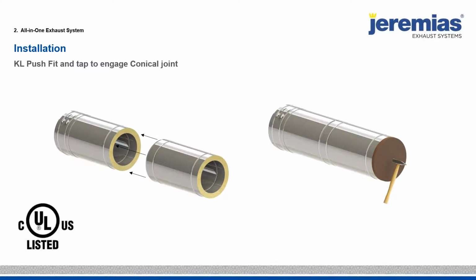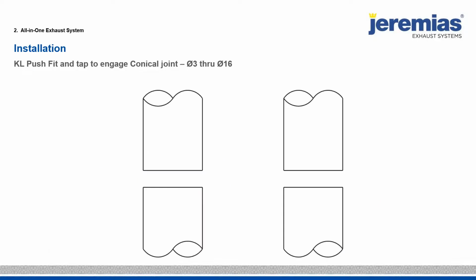So this is a conical system. This is what's used on the smaller diameters up to 18-inch diameter or 16-inch diameter. It's a very unique system. We say it's a push to fit and tap to engage. So this is a conical system that was actually invented by Jeremias back in the 1980s. The patent is up, so this is more of the standard pressure stack system used in Europe for all condensing appliances and even other applications. So this is the standard in Europe, and we're bringing this into the American market.